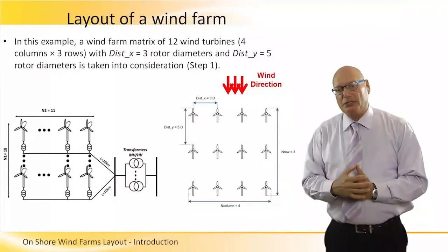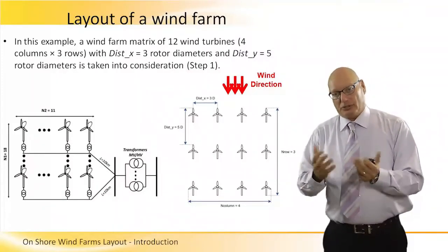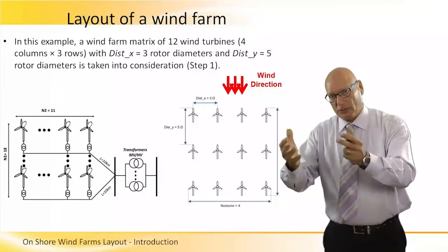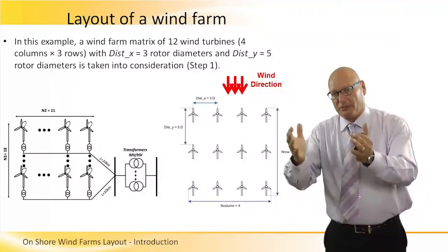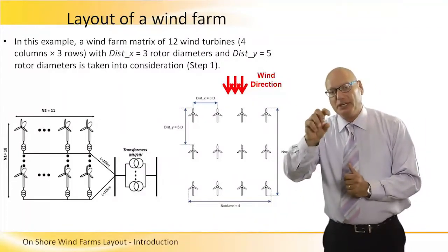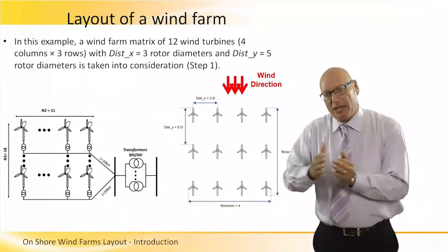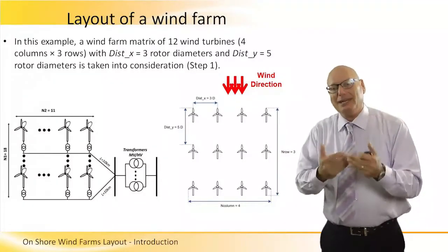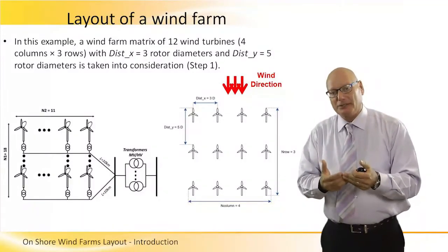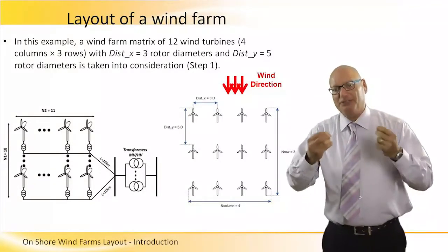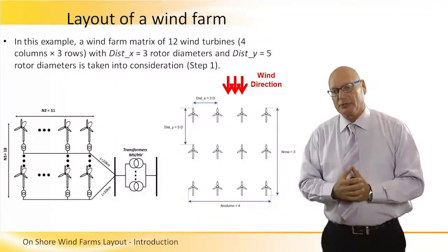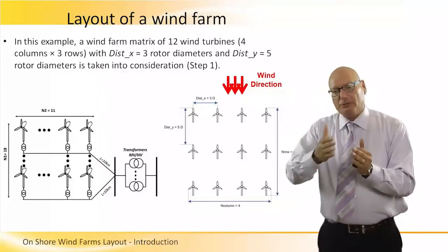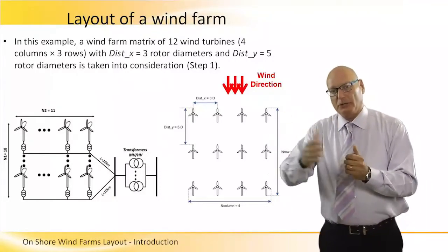On the right-hand side we see another configuration of a wind farm, which again can be offshore or onshore. The distance between each neighboring turbine should be at least five times the diameter of the rotor when going from row to row, and three diameters when going from turbine to turbine within the same row.